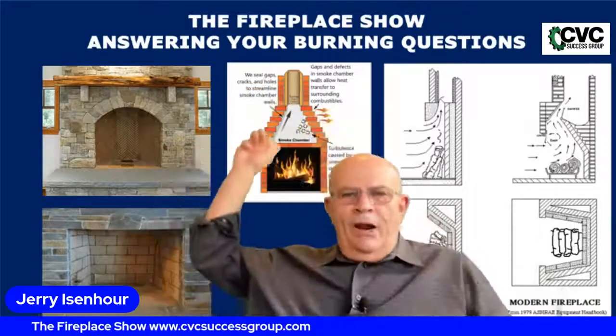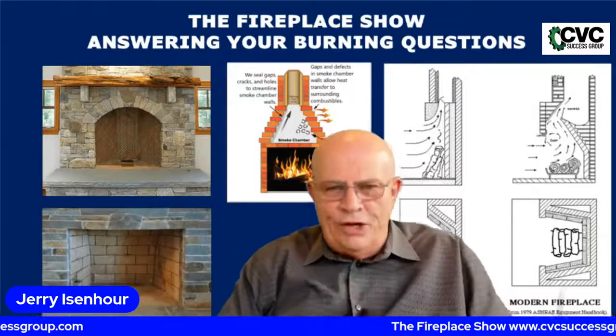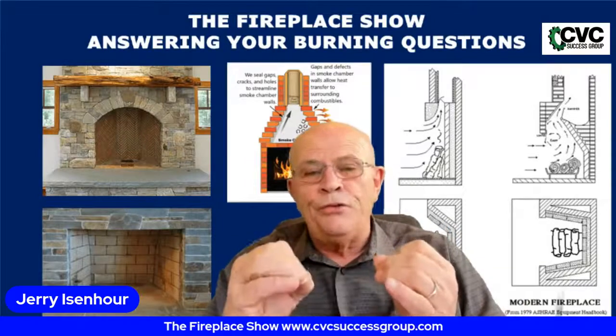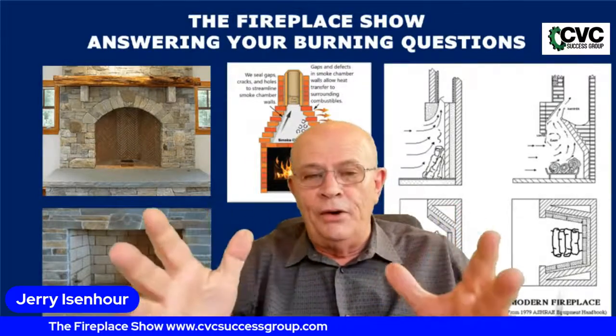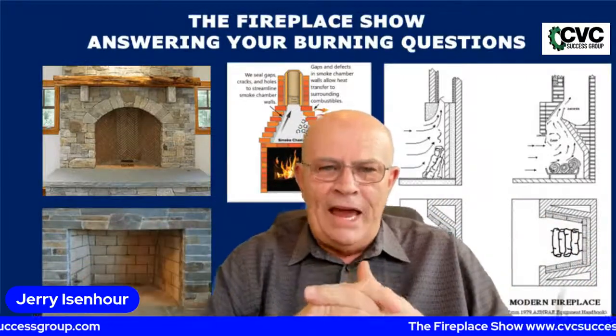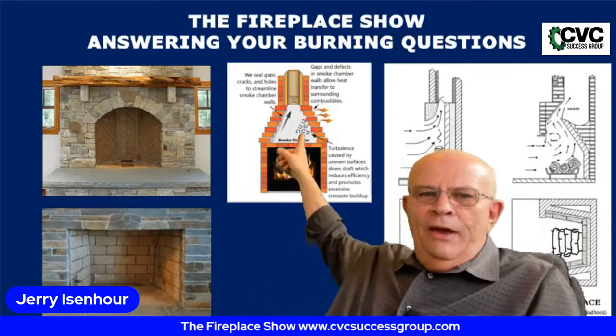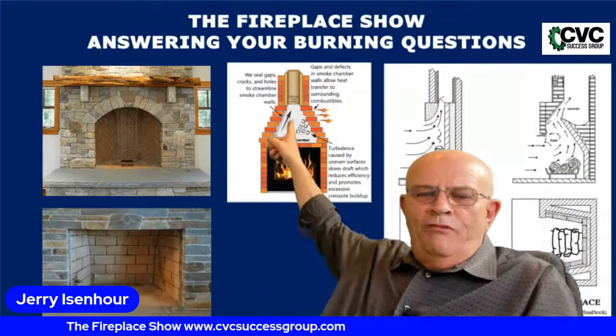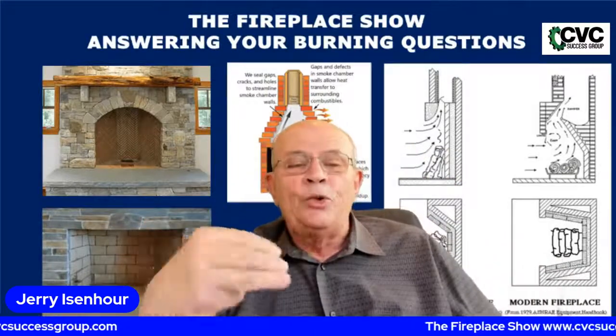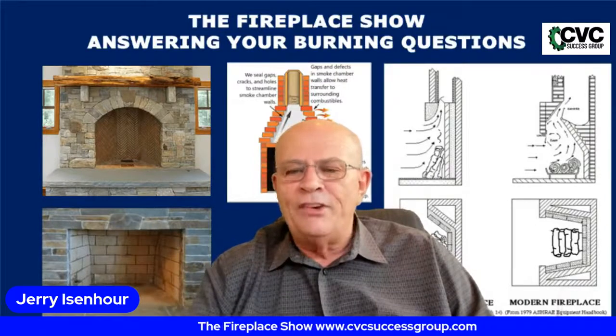You can see that right over my head here, I've actually got a cross cutaway of the smoke chamber. The smoke chamber is the area between your damper and where your flue starts. You may call it the flute. You may call it any number of things, but that's the way a fireplace is designed. And many fireplaces have very rough corbelled edges, like you can see here in the drawing, where we've got these rough bricks. Again, what we're trying to do in fireplaces today is create great laminar airflow, so the smoke and the gases will escape out rapidly.